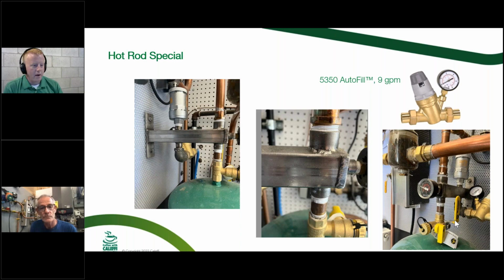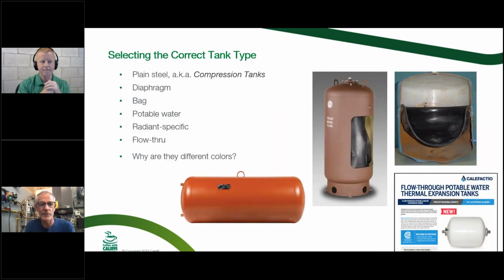Yeah, and I'll bring up too, we get quite a few questions on the tech support calls regarding what they think is a failed fill valve. Like you've got a fill valve here for your boiler that's maintaining a set pressure, and if it goes over that, you automatically think, well, maybe it's a bad fill valve. What I would suggest in those scenarios is to also consider the expansion tank. What we usually recommend is to get the system cooled down, set your static pressure, isolate the fill valve, and then fire the boiler up and see what happens. If it starts going up, chances are it's your expansion tank and really nothing to do with your fill valve whatsoever. All right. And that happens to be our high flow fill valve, a 9 GPM valve.